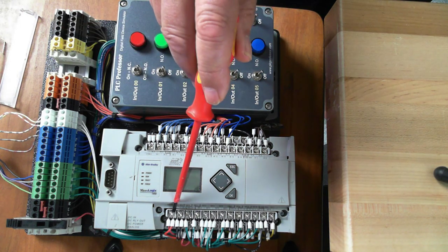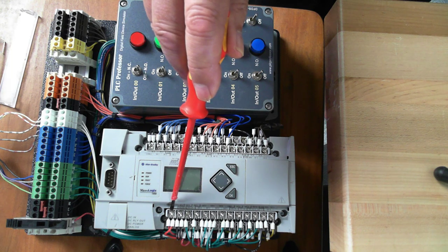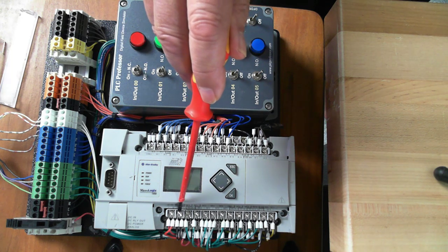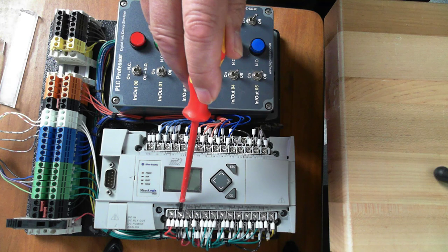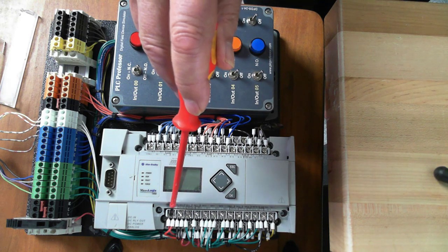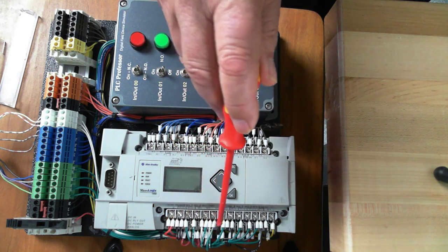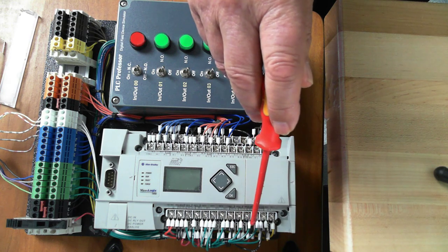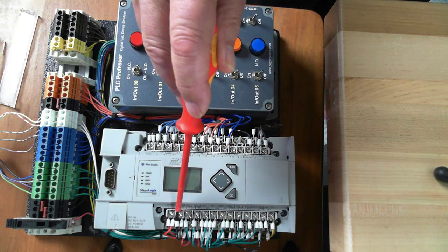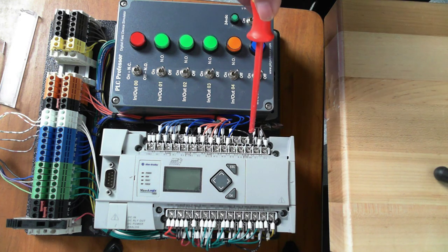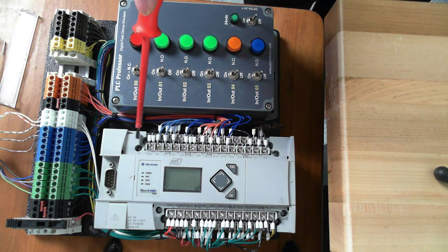Now, if you look close, you'll see this is the plus 24 volt DC input, and this is the, if you want to call it, neutral or 0 volts DC. So this red is jumpered to all the common plus terminals all the way out to here, and then the negative is connected to just a couple here, whereas most of the 0 volt DCs are on this side.